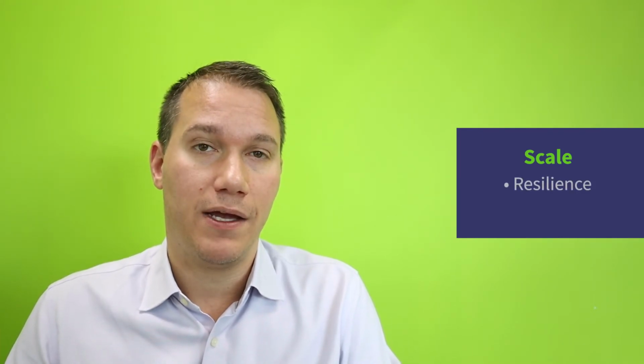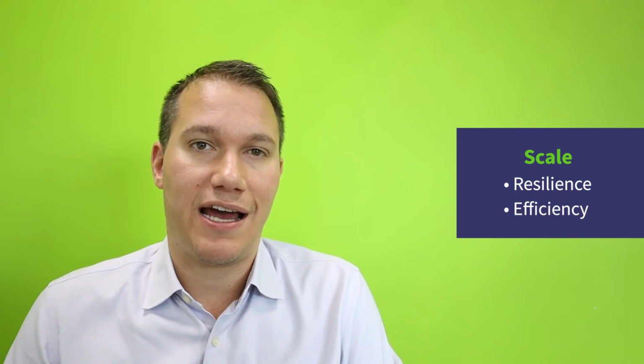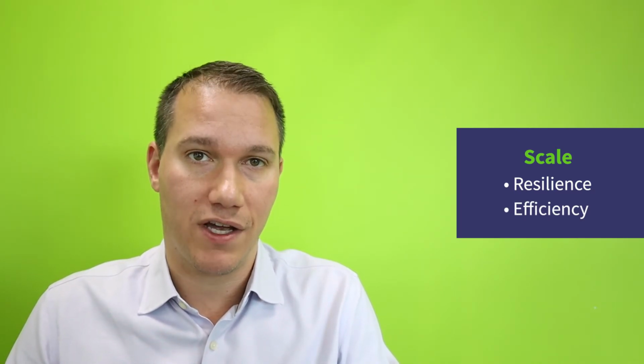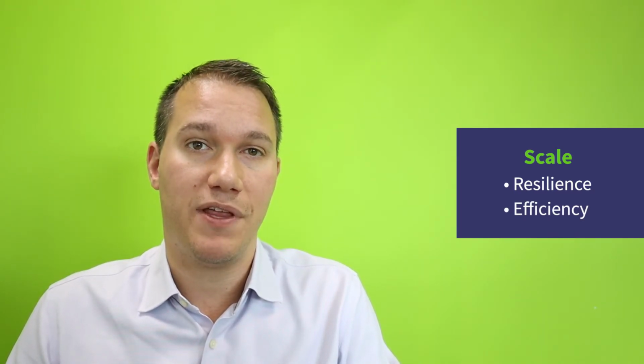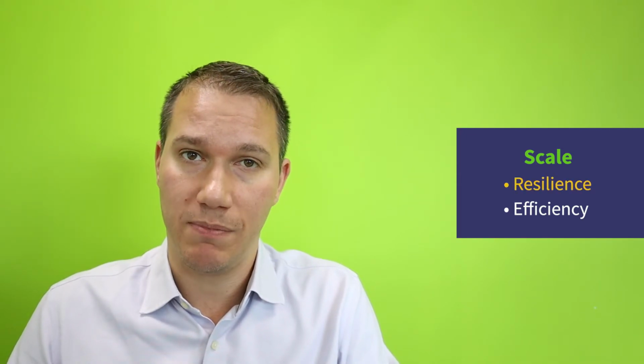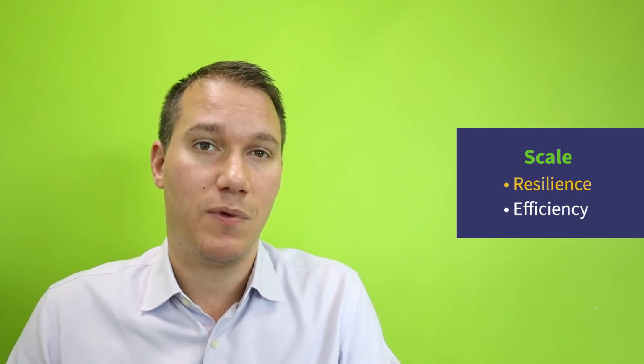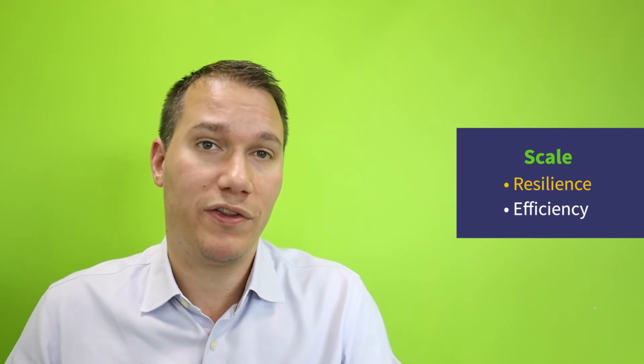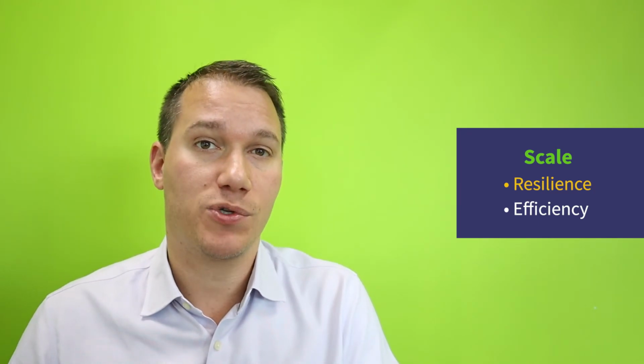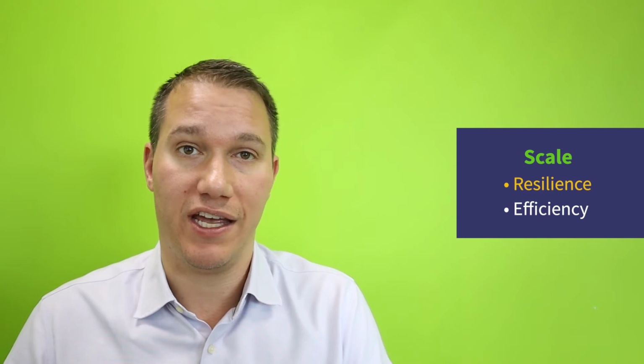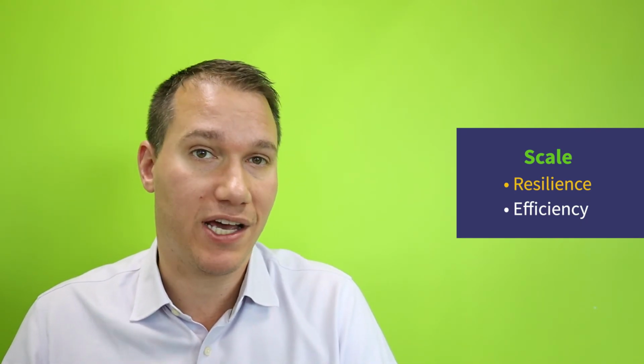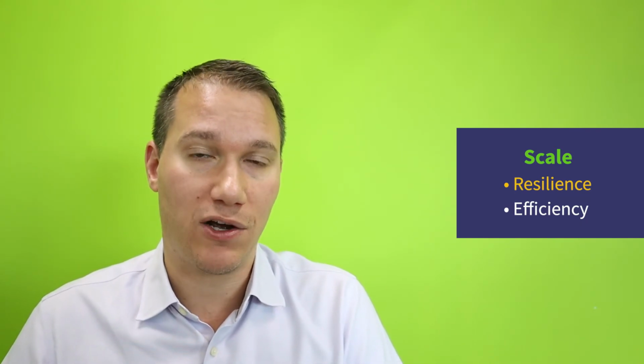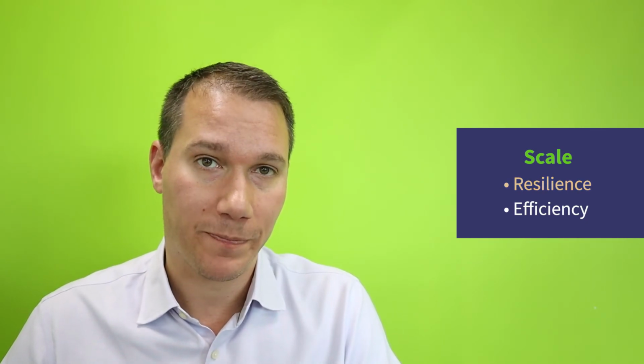The first factor is scale, and with scale comes both efficiency and resilience. Data centers are designed to house hundreds of racks and thousands of servers, so from the ground up they build their UPSs with resilience in mind. Typically they will have not only one, but actually one UPS per feed, and they'll also have an extra UPS per feed so that if there's an issue with any UPS in line, they've got one to fall back on. That's referred to as N+1.